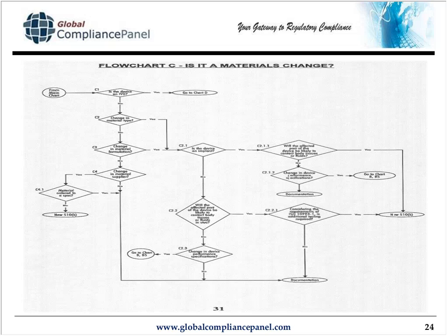So what I'm looking at now is biocompatibility. And if the answer is yes, the device is an implant in 2.1, it will or is likely to contact body tissues or fluids, that's a new 510K right there. Even if the testing has already been performed, you are required to submit a new 510K. However, if C2.1 is no, and the device is not an implant, that takes us to C2.2.